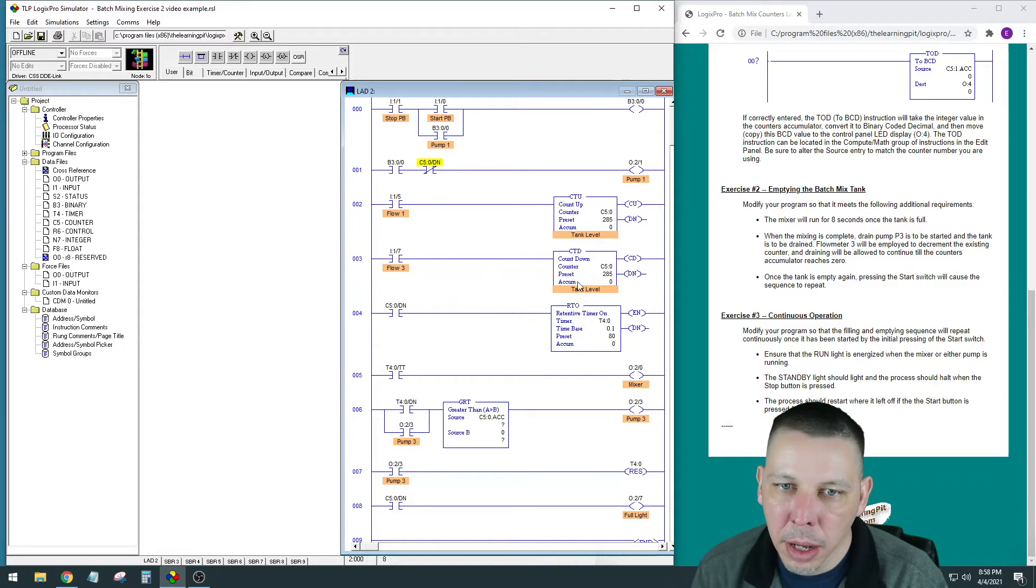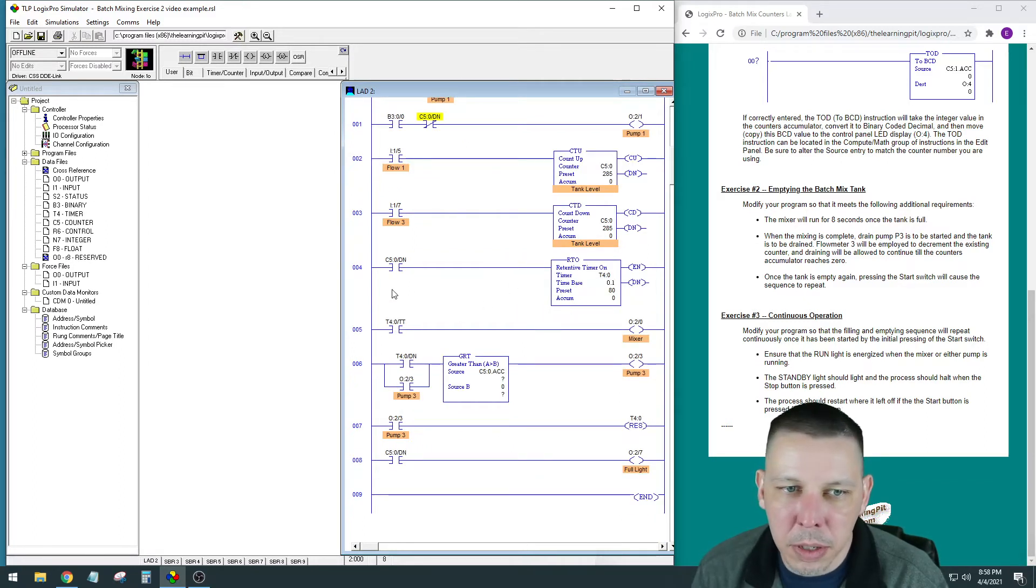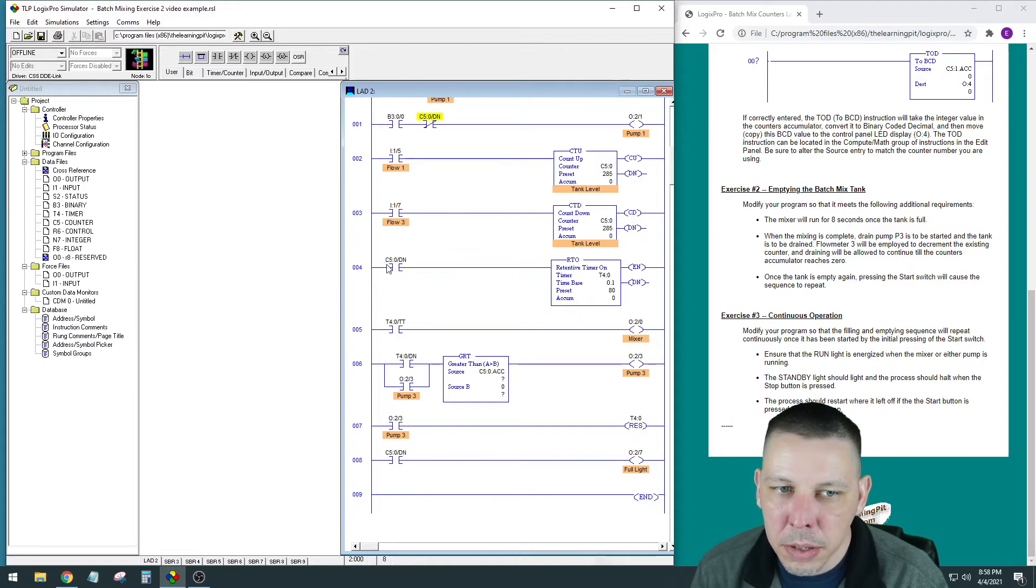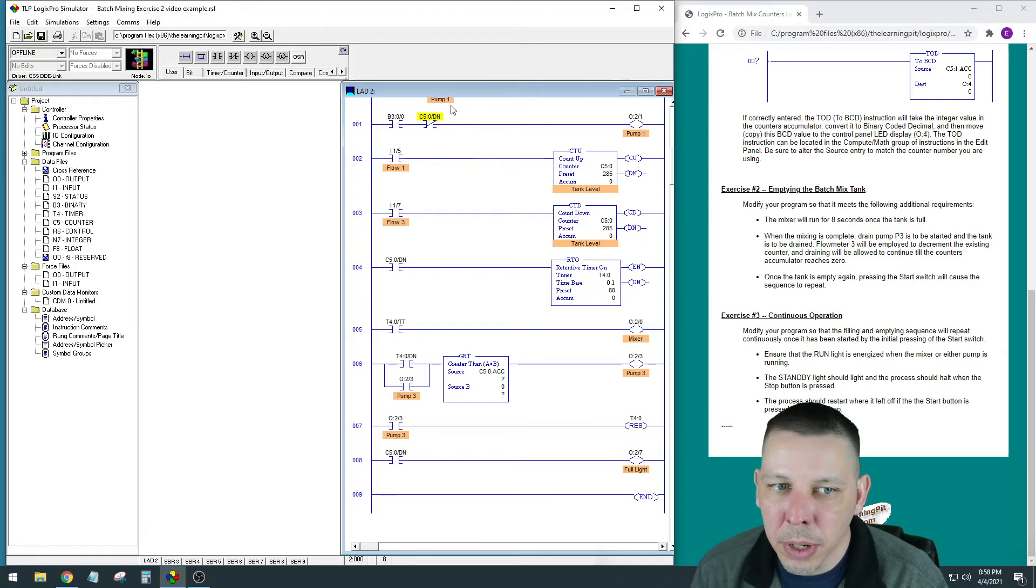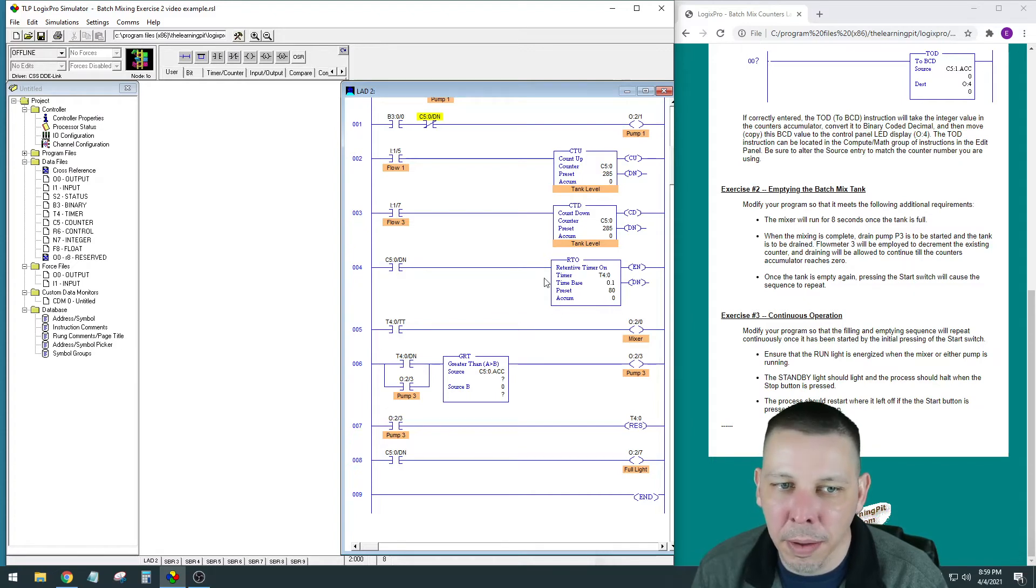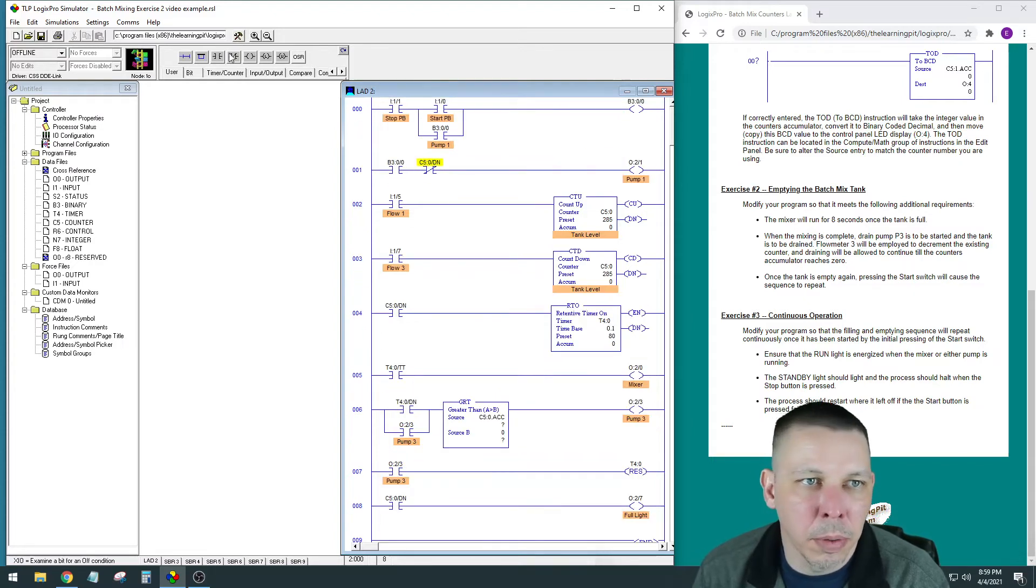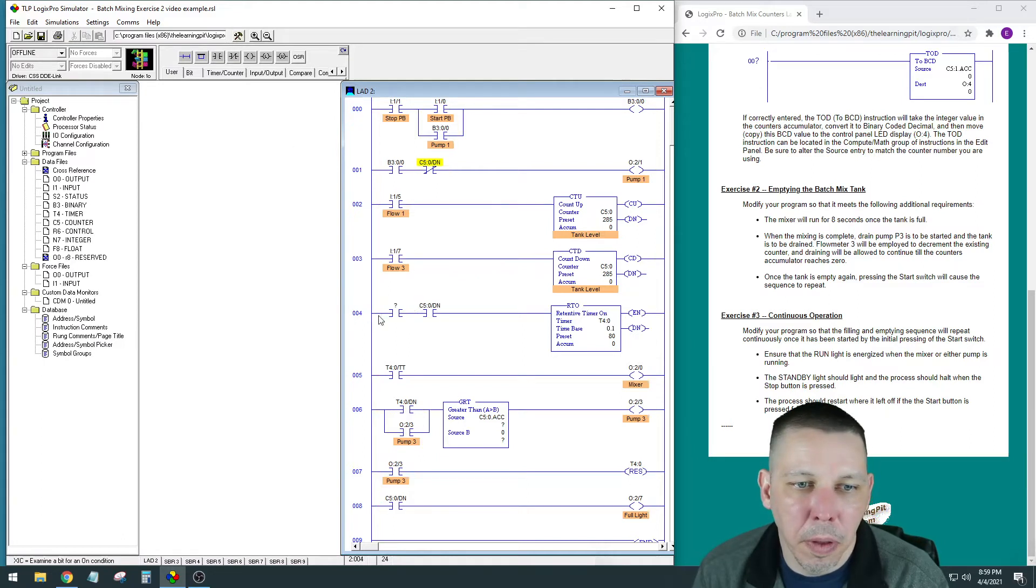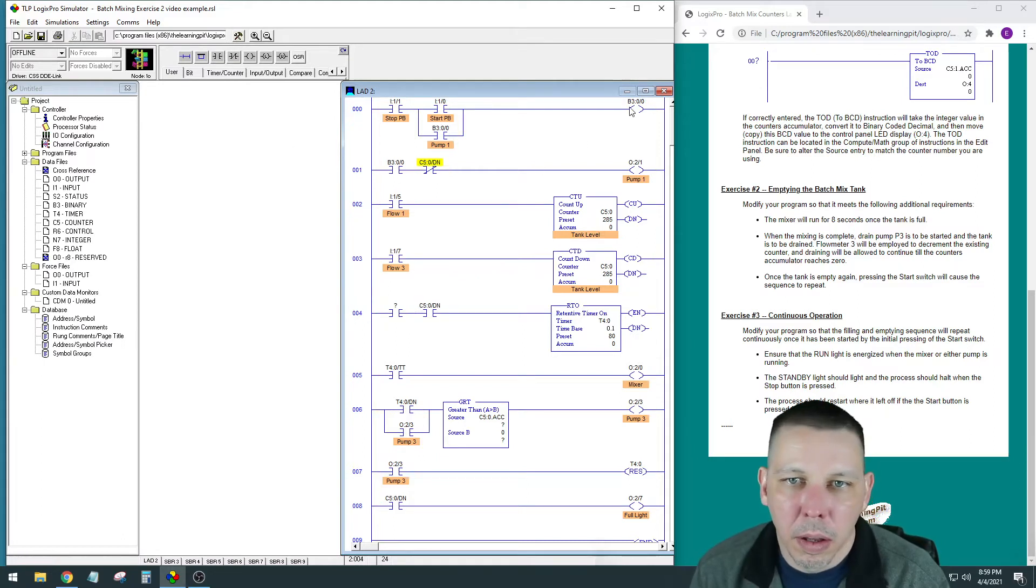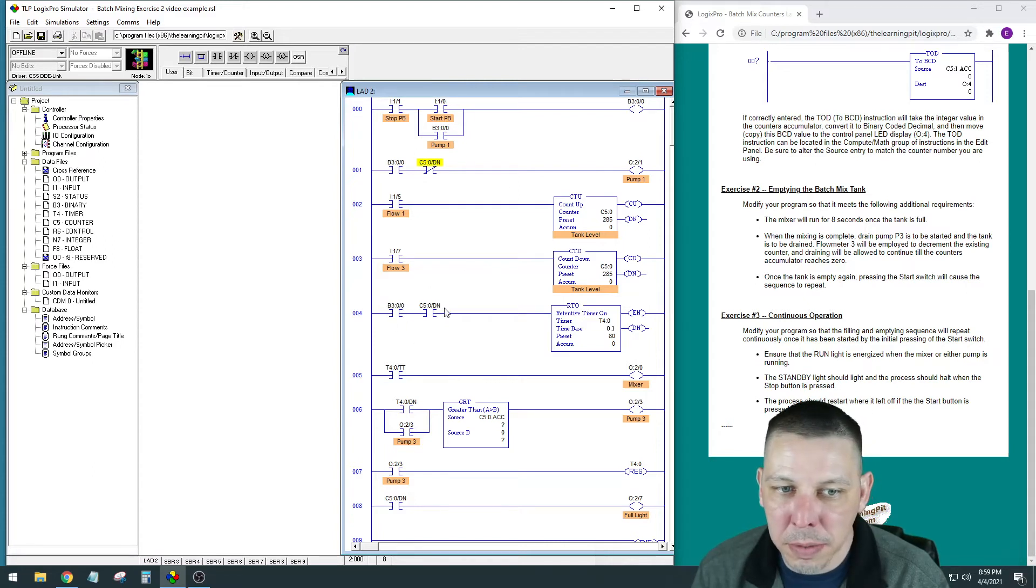We do want to stop this timer, because C5.0 will be done, and if we hit the stop button and we don't have anything to interrupt this, C5.0 is still going to be done, so the retentive timer is still going to continue to count. So we are going to need one of those here. Now when we press start again, it'll enable this because C5.0 will still be done.